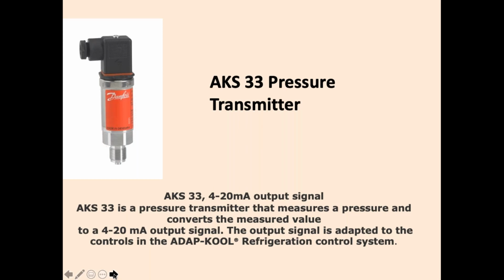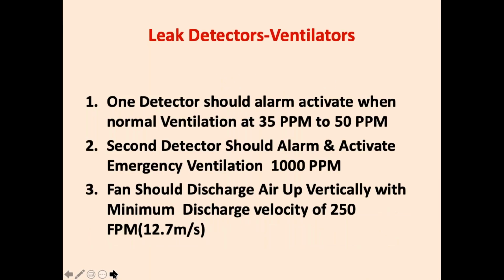They will give a 4 to 20 milliamp signal output, and then you can put it into your control panel, whichever SCADA system or PLC panels you are using in your plant. Leak detectors are very, very important. Leak detectors should be in the plant room. One detector alarm should activate normal ventilation at 35 ppm, because I mentioned last time that 25 ppm can be detected easily by any human being by nose because of the smell. The second detector should activate emergency ventilation at 1000 ppm, and the fan should discharge air vertically up with a minimum discharge velocity of 250 fpm.